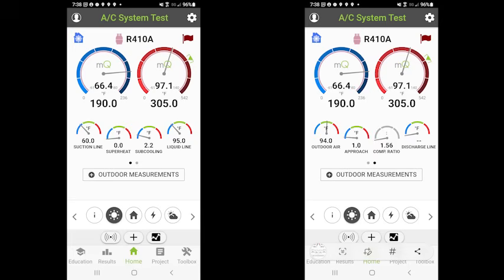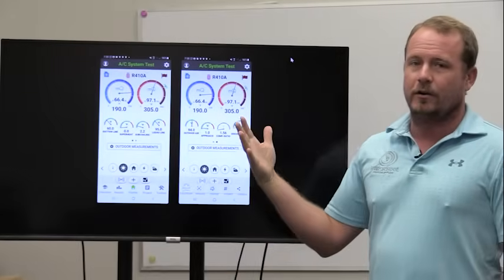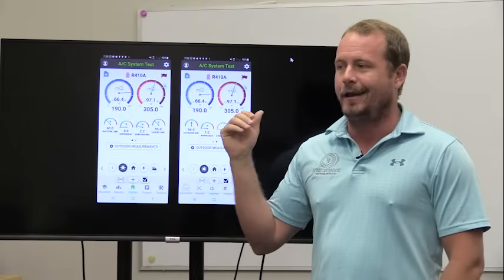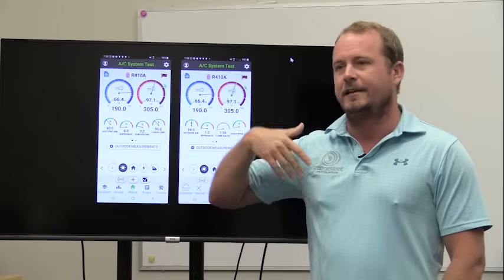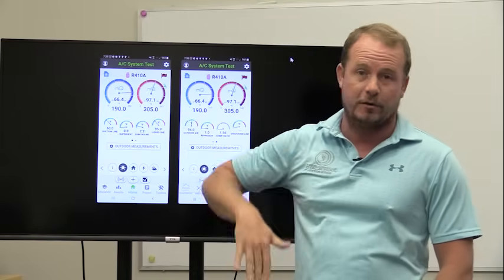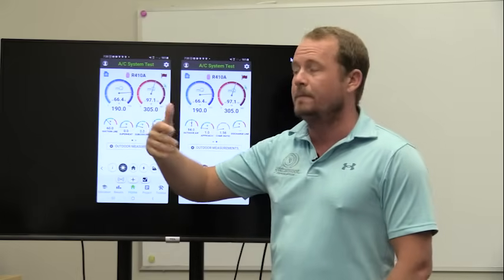What are some of the other indications? Well, an easy way to think about this that kind of summarizes all of this is compression ratio. So here we show a compression ratio of 1.56, which is definitely low. Typical modern equipment, you're generally going to see compression ratios around 2.3. And that can vary a little bit. Obviously, you get a much hotter summer day, compression ratio is going to go up. You have somebody who wants to keep it really cold inside their house, compression ratio is going to go up.